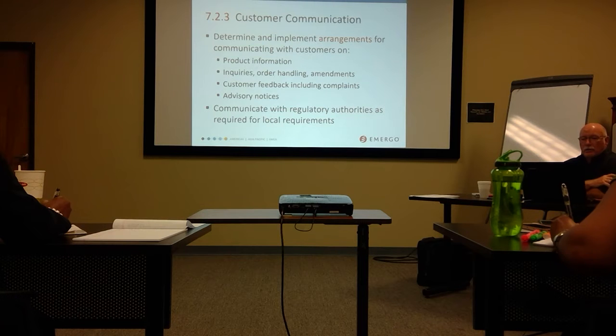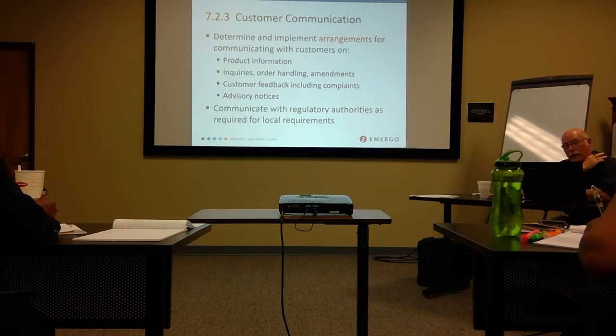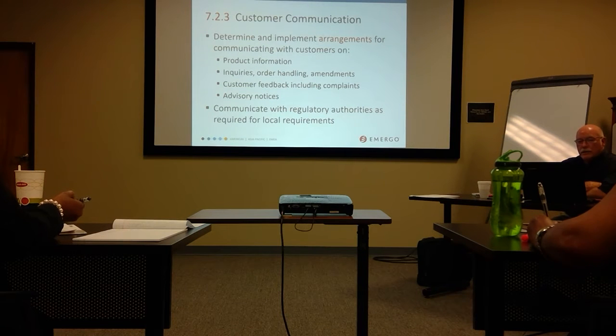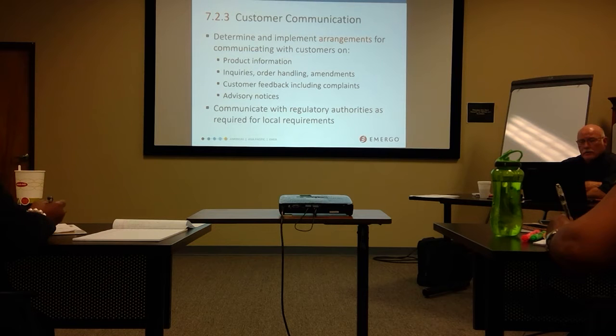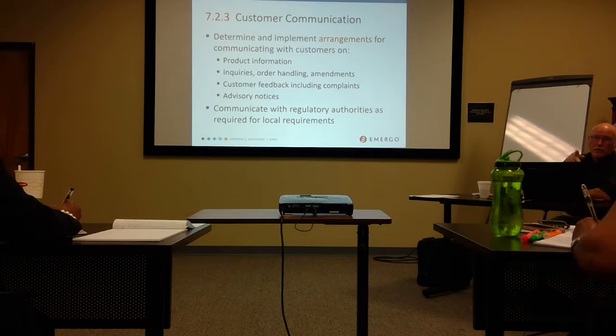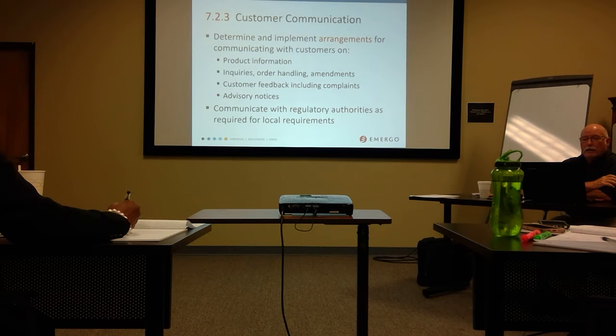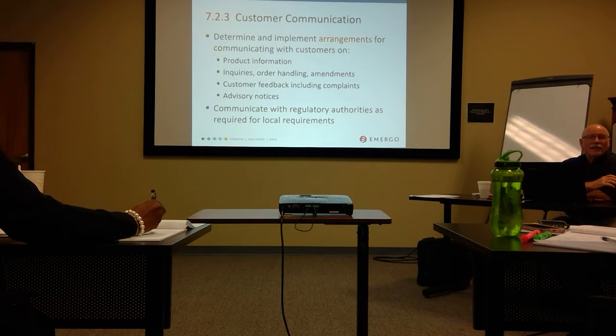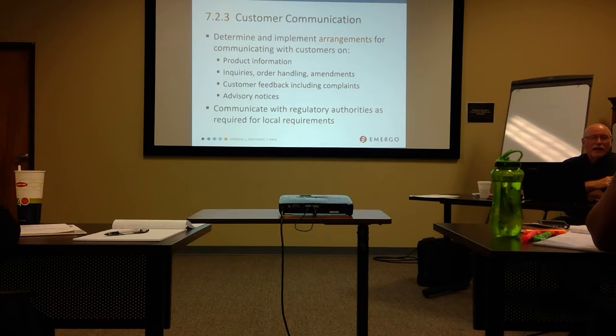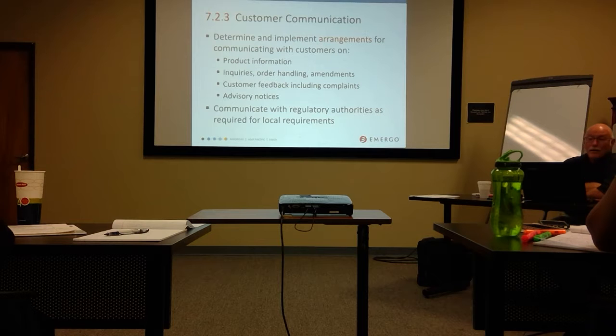Customer communication — part of the information when you have processes for this. Question or feedback — we will talk separately about that. It's a critical process. Number one and number two of FDA's warning letter topics are the complaint system and CAPA, and they trade places year to year. The complaint system is critically important. FDA spends a lot of time on it. It will get you a warning letter if it's not done correctly. A customer in Florida got a warning letter on the complaint system because in their document they actually said, 'if we can't reproduce the complaint, it's not a complaint.' FDA viewed that and issued a warning letter.